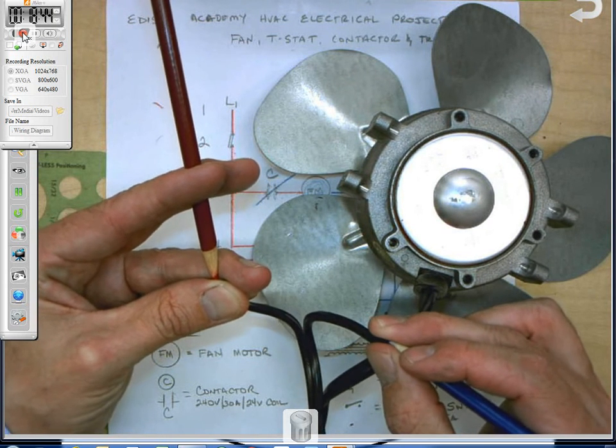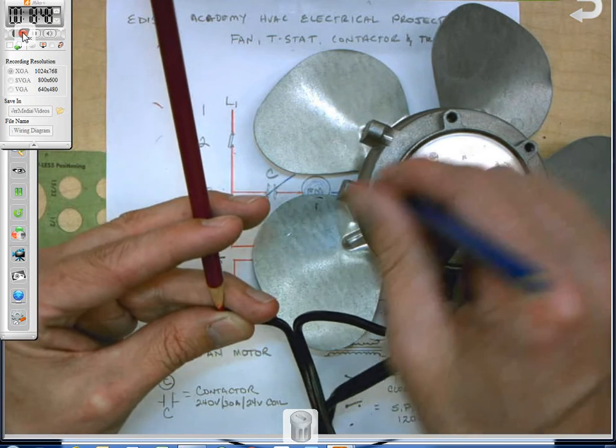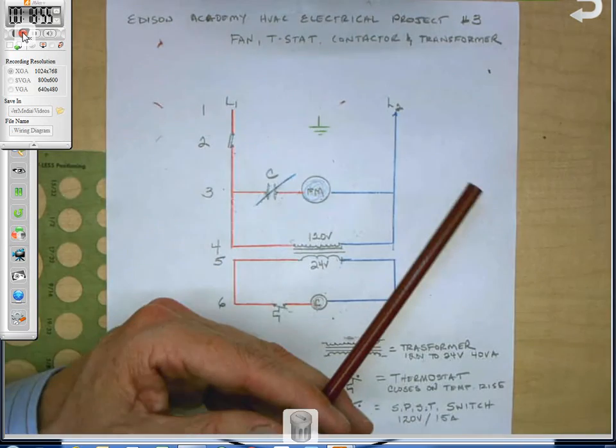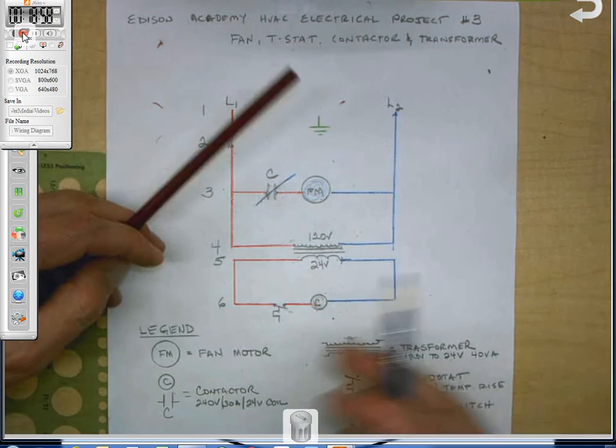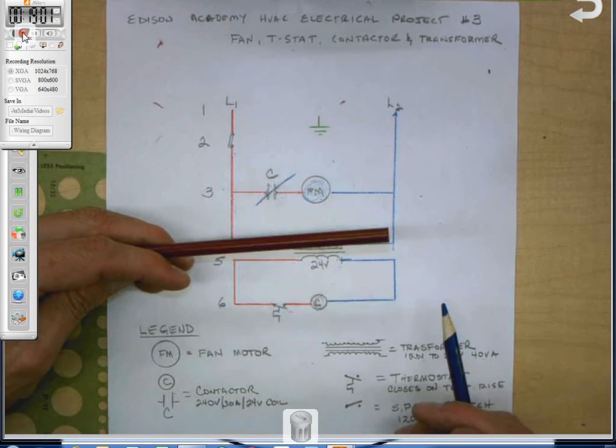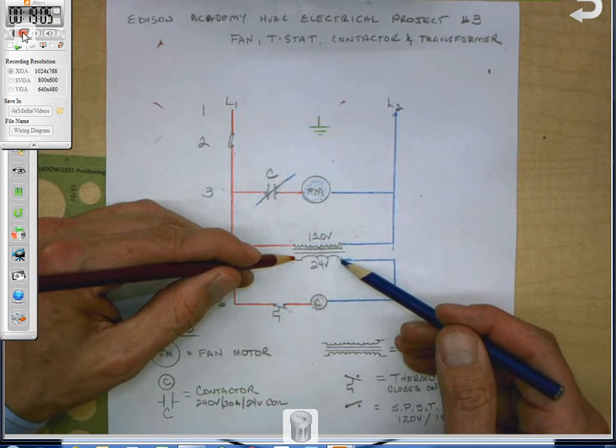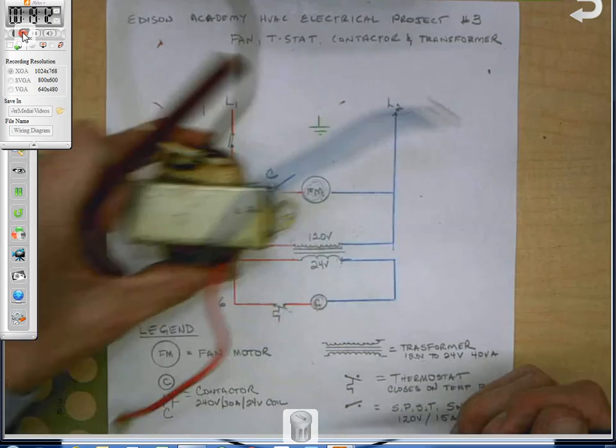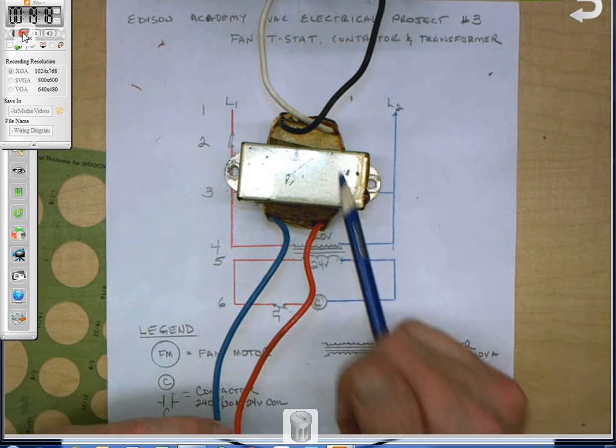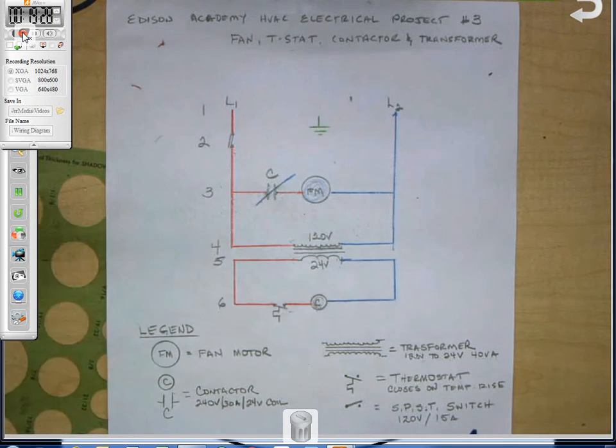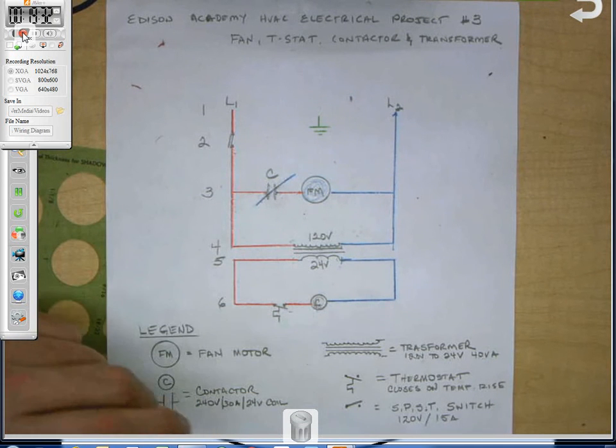So that's some ways with this one that you could use this for troubleshooting three or four different ways. If I'm reading 120 volts here, but no 24 volts there, what's that mean about this part right here? If I got 120 volts on this side, but I measure, I got to wire it up to the contactor, and I'm not reading 24 volts here, what does that mean about this part? Transformers bad. It's not inducing the power to the other side of the coil. So, change out the transformer. That's the disconnect. That would be like this switch here, but that disconnect was a blade type disconnect, and it melted because they had one of these wires touching the ground, and they didn't test it with the meter before they tried to plug that back in, and it shorted, and when it shorts, it gets really hot. It still works.